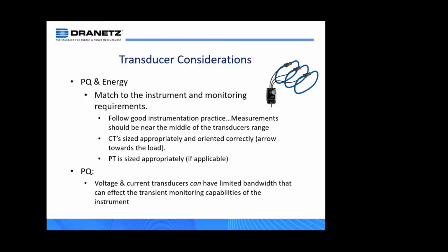And phase accuracy is going to affect parameters such as VA and power factor. Those are all things that are involved in energy management. So if you want to be most accurate in that regard, you want to make sure that you're not in the under range situation. And again, instruments like the Dranetz instruments will actually indicate when you're under range.